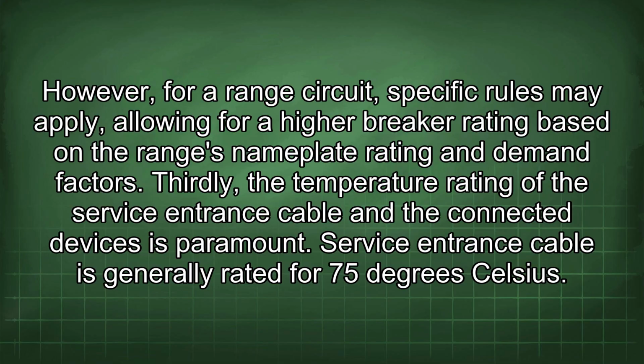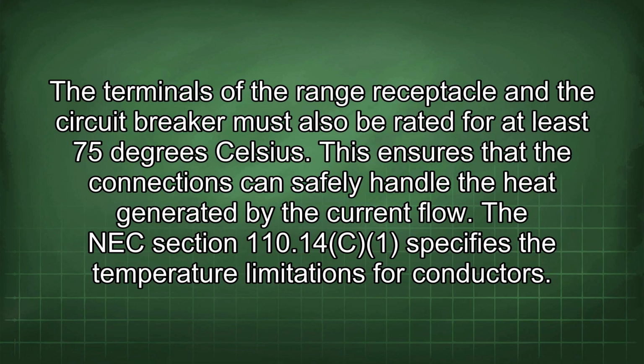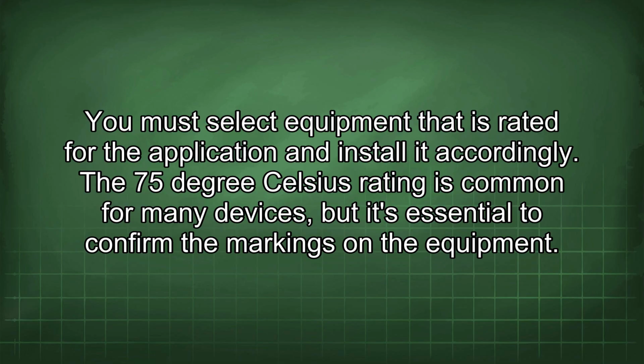Service entrance cable is generally rated for 75 degrees Celsius. The terminals of the range receptacle and the circuit breaker must also be rated for at least 75 degrees Celsius. This ensures that the connections can safely handle the heat generated by the current flow. NEC Section 110.14 specifies the temperature limitations for conductors. You must select equipment that is rated for the application and install it accordingly. The 75 degrees Celsius rating is common for many devices, but it's essential to confirm the markings on the equipment.